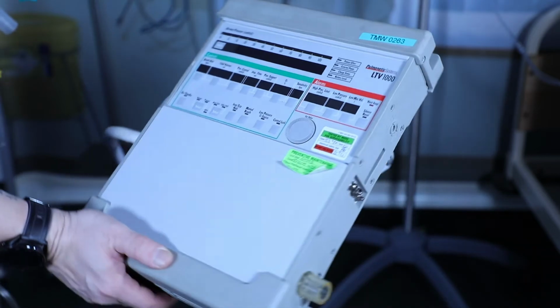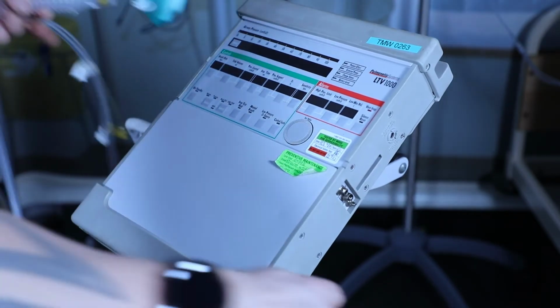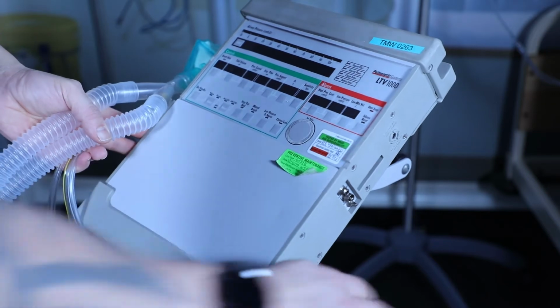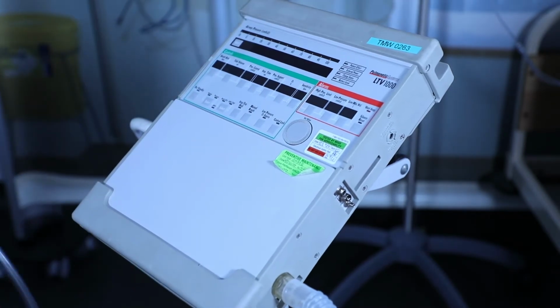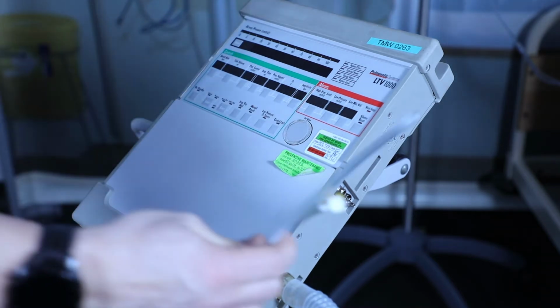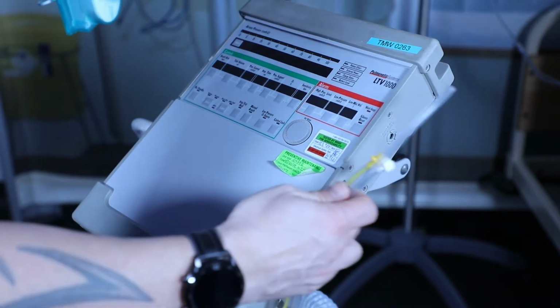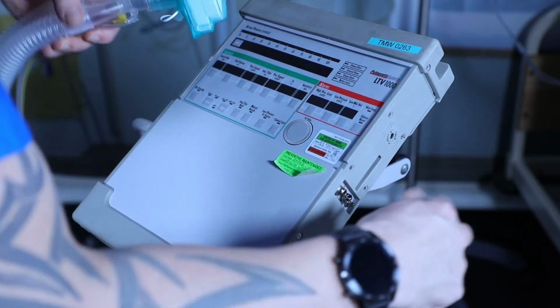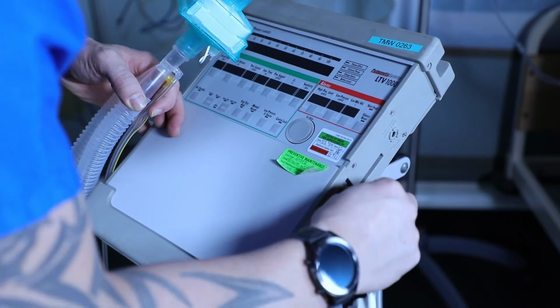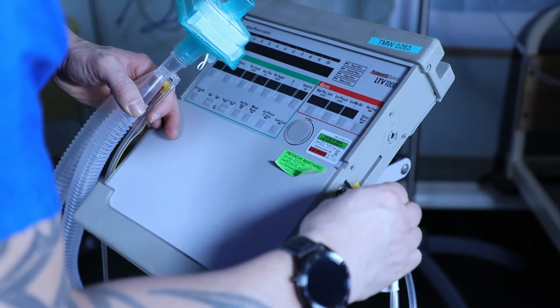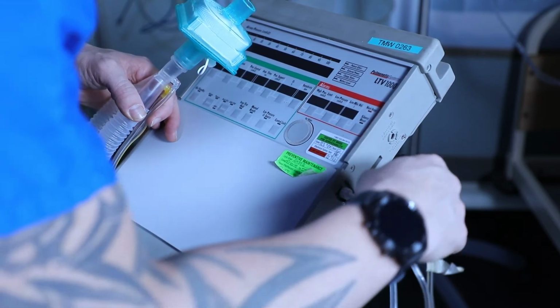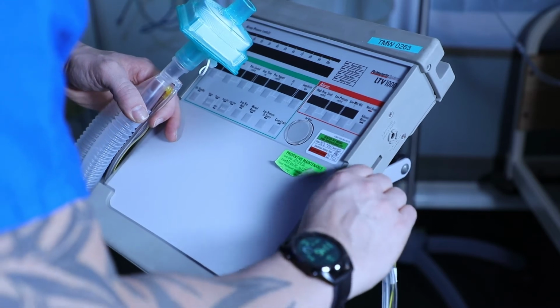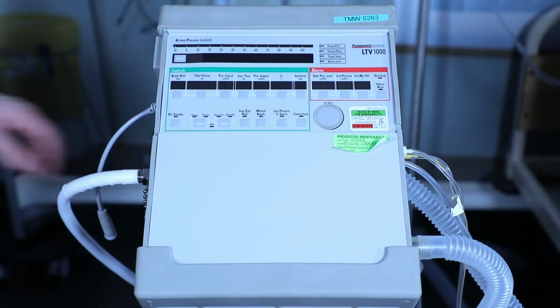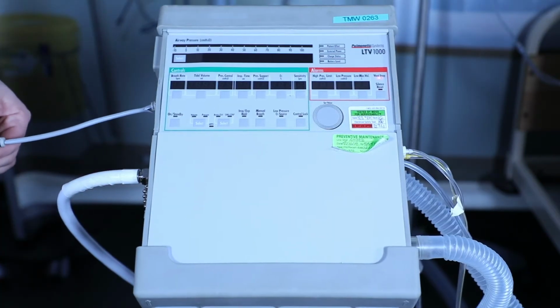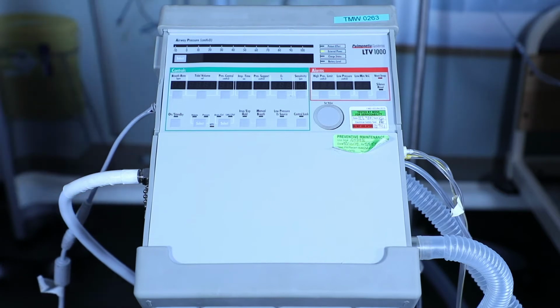We then need to connect up the test patient circuit, the elephant tubing secures to the bottom. Then we have 3 sensors which have to attach just into the middle of the ventilator. Each sensor connection can only attach to its opposite part, so the exhalation valve to the bottom, the yellow low pressure sensor to the middle and the white high pressure sensor to the top, and we just need to ensure that these are secured firmly. The final thing we need to do is connect the LTV up to its mains power supply.